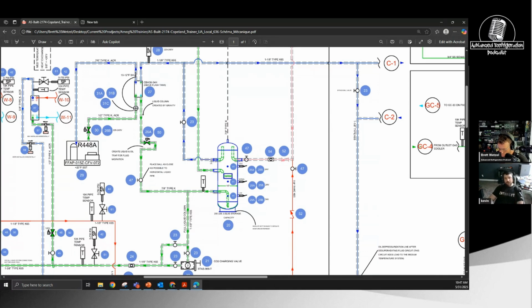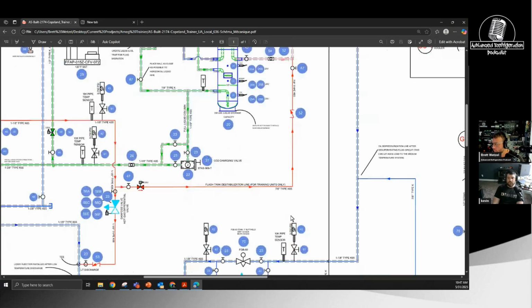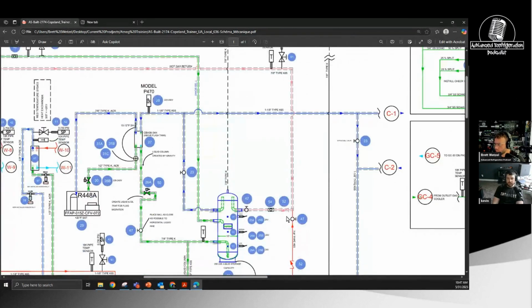This is a little weird because where you got 47 flowing into the receiver, there's what they call a flash tank destabilization valve. Now, because this was a trainer, they were taking the discharge of a low temp, boosting the pressure up with a Danfoss inlet pressure regulating valve, and dumping it into the flash tank to build heat to make it seem like the flash tank was destabilized. So basically, when you throw an input on the E3, it would inject hot gas in there and show guys what happens when the flash tank's all destabilized and the rack can't keep up.